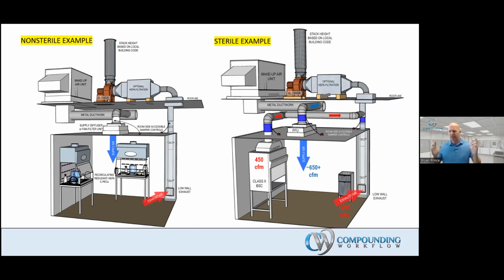I don't know who on the expert committee thought that that was a good place to land a negative pressure room, but it's a hard place to land without fluctuations, without getting too much into barometric pressures and envelopes and the whole clean room physics. Understand that's a very tight gradient. So the more hoods you connect to that Rubik's Cube, the more difficult it's going to be to balance that negative pressure space.